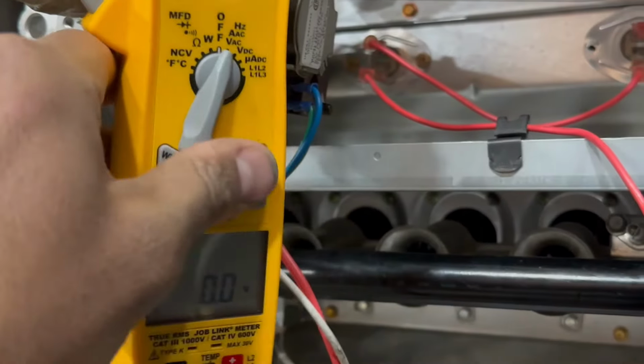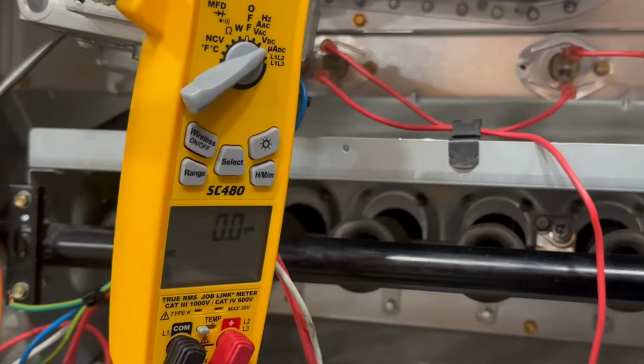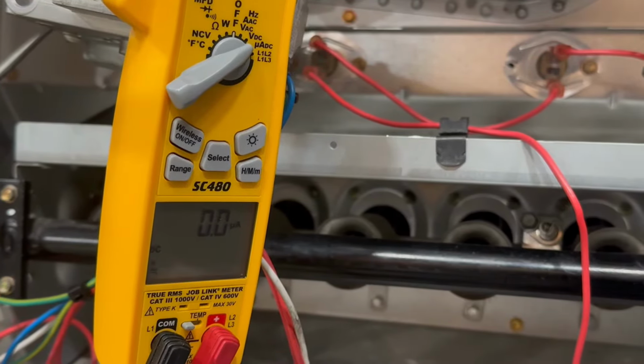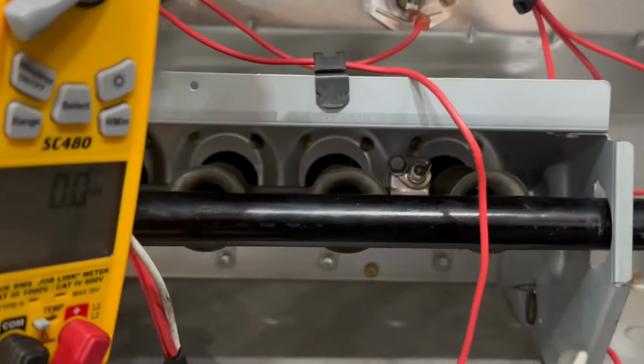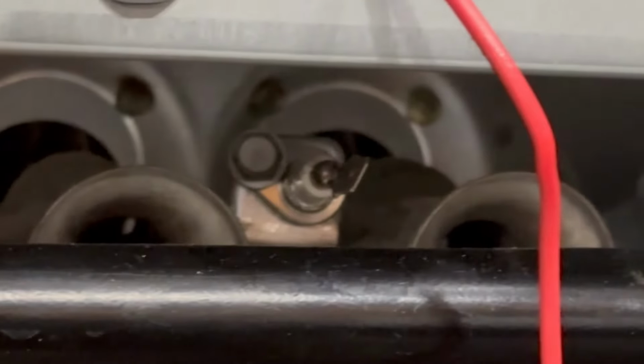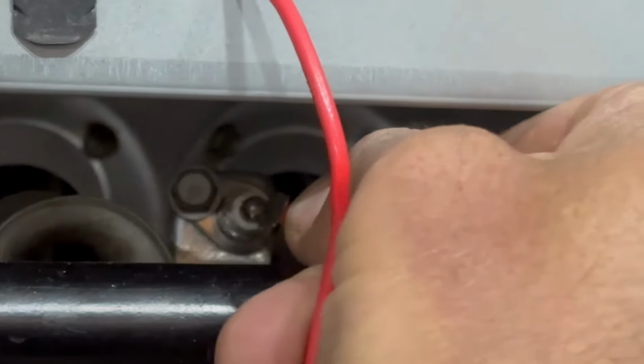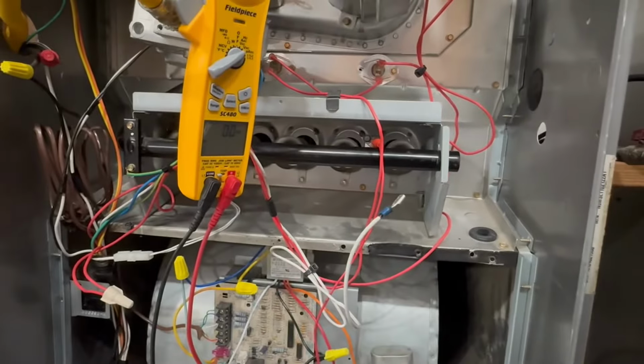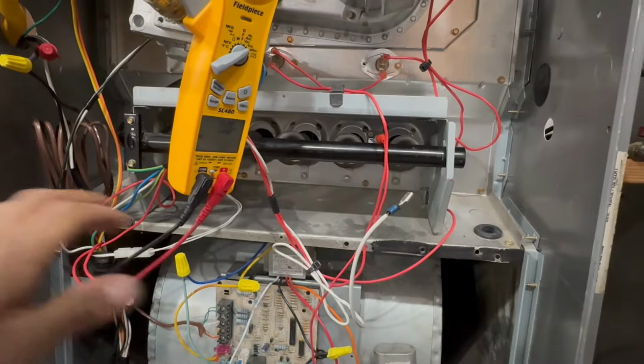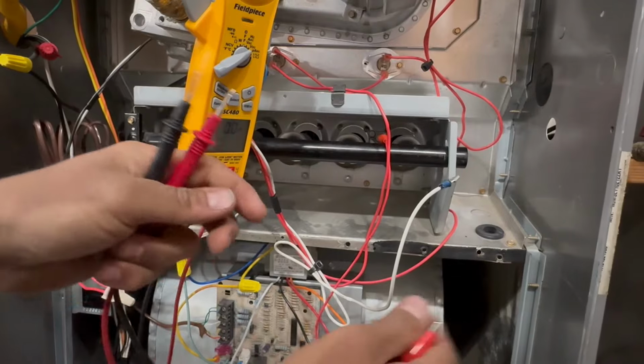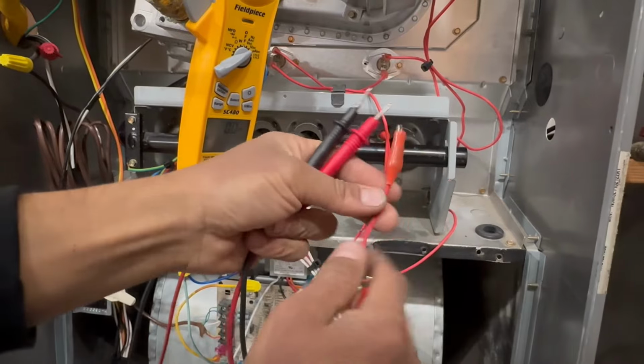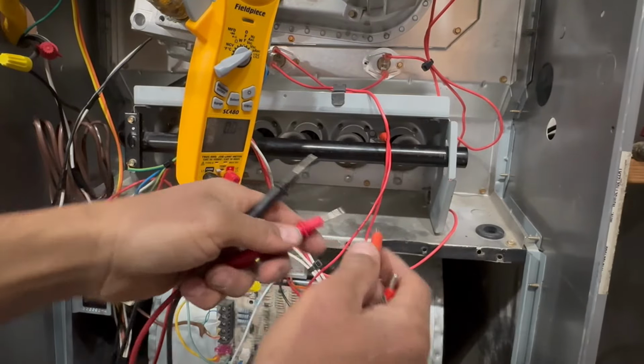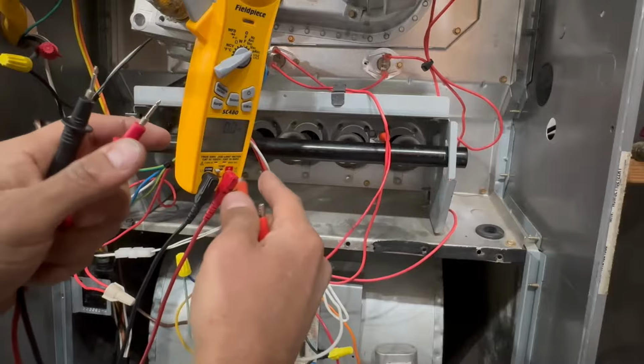The setting is microamps DC. This is what I do when I check microamps. First, you put it on that setting, and I actually get two alligator clips because they make your life easy. Right there, I have that male connector. I put one here, and of course, there's no power, I make sure there's no power. Then I've got my two leads right here. The alligator clip I put on the flame sensor, and it doesn't matter which one is which. You might get a negative number, but all I care about is the number.